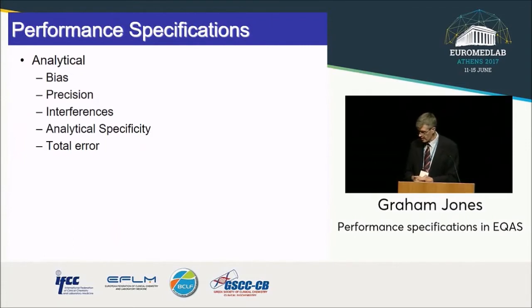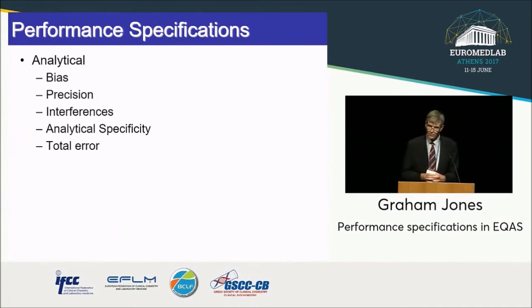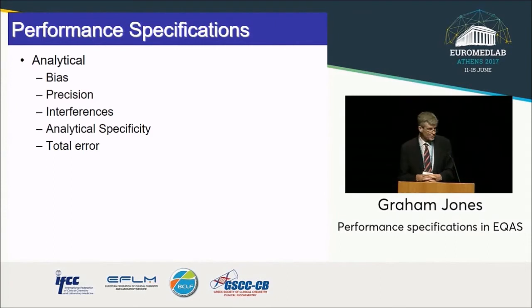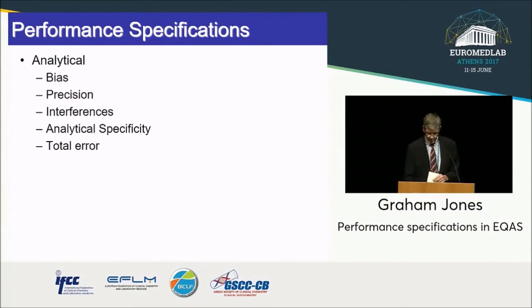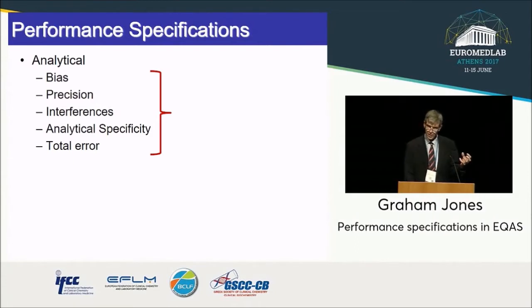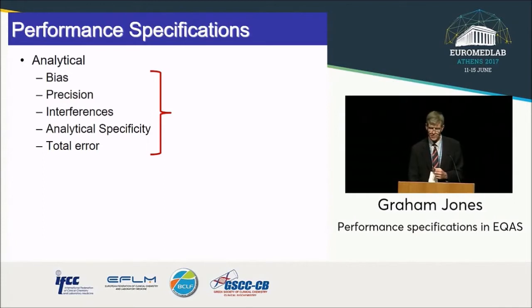As touched on in the previous presentation, in the analytical process there are a number of factors which go together to make up the final result: the bias, the precision, and I'd certainly include the interferences or influence factors that might be caused by the analytical specificity — or we might combine those in various ways to make total error. We can consider analytical performance specifications for any or all of those, and we then need to think about where in our routine laboratory practice we might apply those specifications.